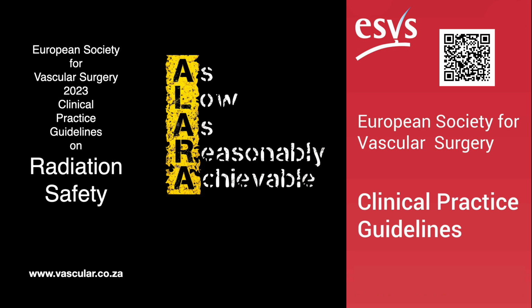However, there's a catch. There's a nuance. While collimating reduces the total dose, it does concentrate the dose on that smaller area of the patient's skin that remains in the beam. So the guidelines caution against prolonged use of very tight collimation focused on one exact spot for too long, as that could increase the peak skin dose in that specific area. It's a physics principle they need to keep in mind. Okay, so narrow the beam to what's needed, but maybe shift the center point slightly now and then if you're imaging the same general area for a long time.